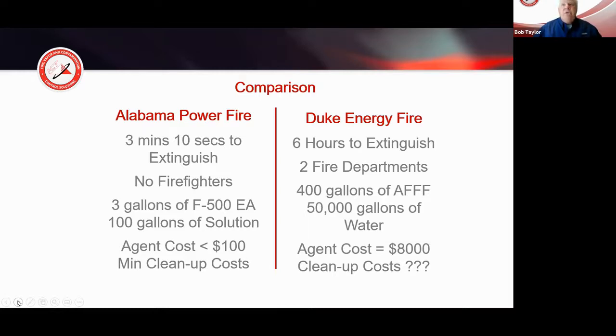Here's a comparison of a real situation. On the right, a utility had a transformer fire that took well over 6 hours to extinguish, involving multiple fire departments, 400 gallons of AFFF, and 50,000 gallons of water. The overall cost for just the agent alone was around $8,000. Who knows what the cleanup cost, because all that liquid runoff and oils have to be contained and cleaned up. But the agent cost itself was $8,000 plus. Now let's look on the left at the other utility's experience.